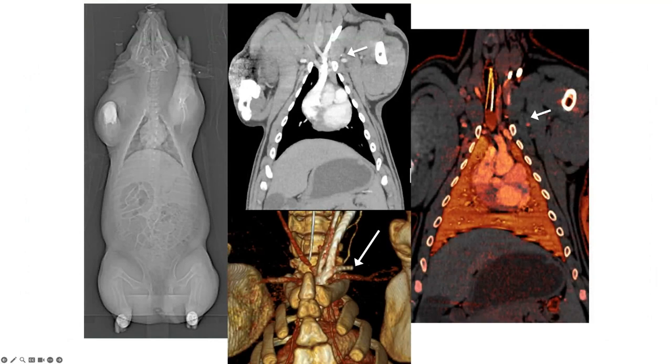Here's another study that was performed to see the safety of this material. In this particular case, we wanted to see whether pieces of the gel would break apart and go downstream and induce embolization in areas that were not the right target. So to do that, we put the material upstream from a large vascular network that can be imaged, like the lung. And in that case, we could see if there are parts of the gel that would break off and basically clot different regions in the lung. And here we can visualize this and look at the lung afterwards. And here, as you can see, by visualization, the lung is open and patent, and no region of the vasculature in the lung has been blocked off.